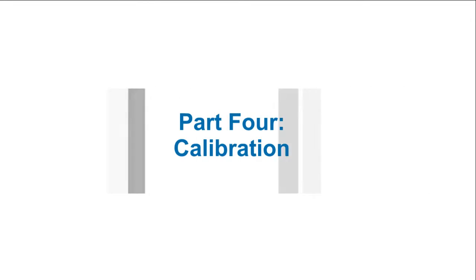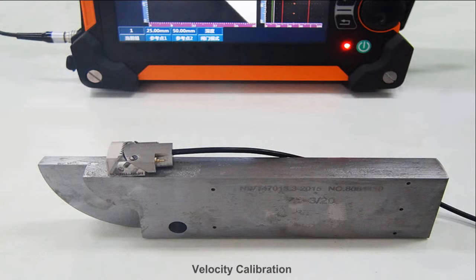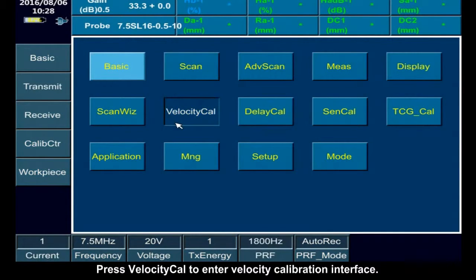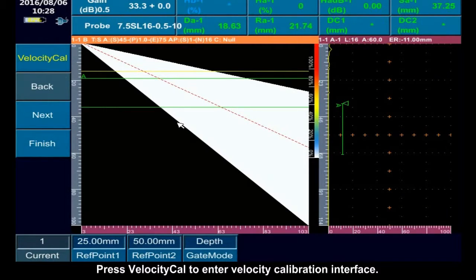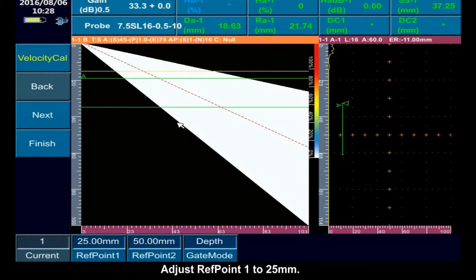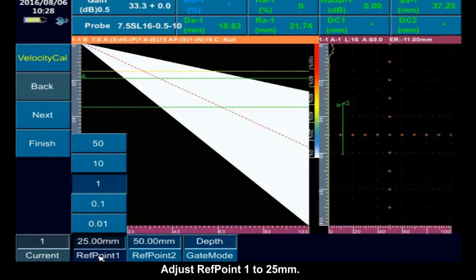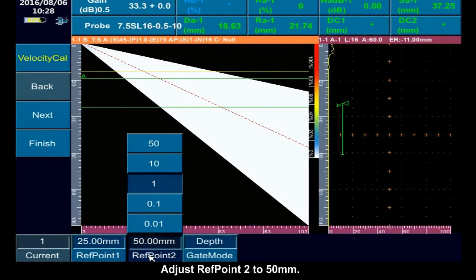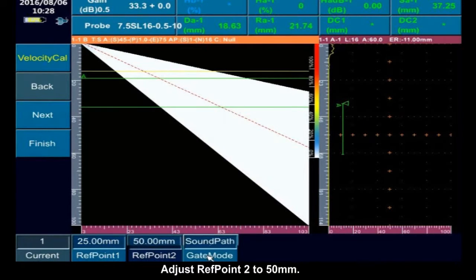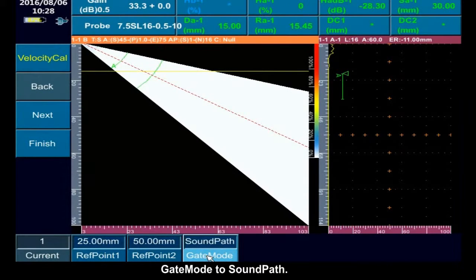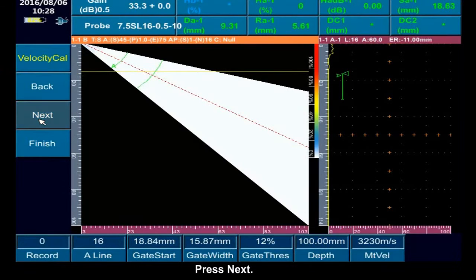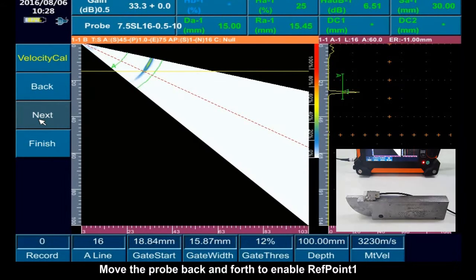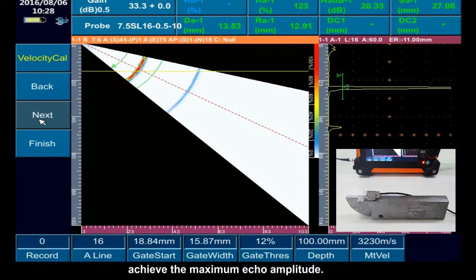Part 4. Calibration. Velocity calibration. Put the probe on the pipe weld calibration block. Press Velocity calibration to enter the velocity calibration interface. Adjust reference 1 to 25 mm. Adjust reference 2 to 50 mm. Gate mode to sound path. Press Next. Move the probe back and forth to enable reference point 1 to achieve the maximum echo amplitude.